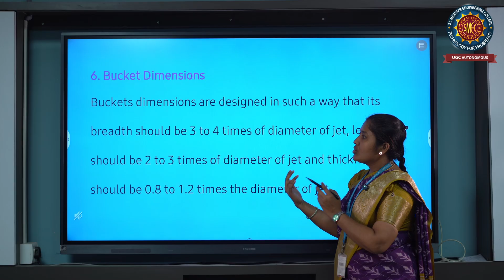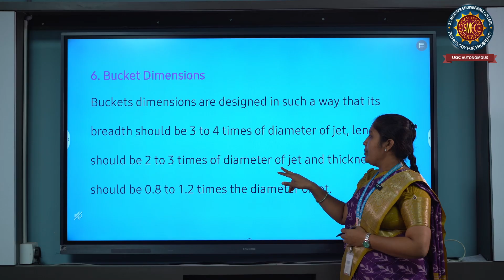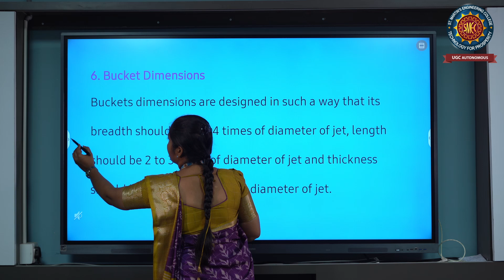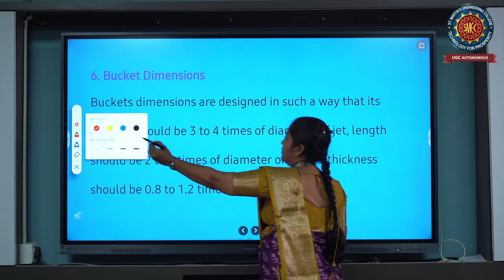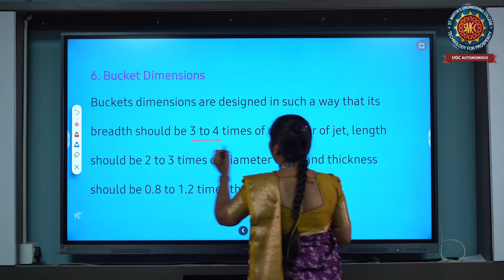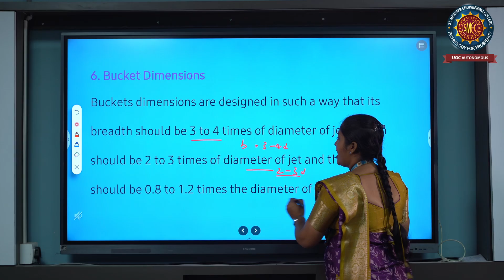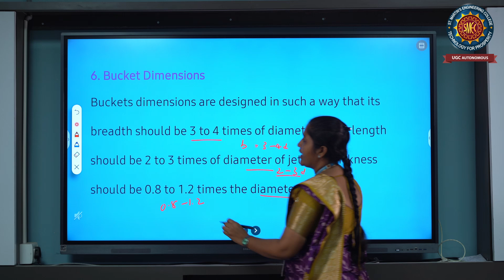And the next is the bucket dimensions. The bucket dimensions completely depend upon the width as well as the breadth. The width should be between 3 to 4 times the jet dia, that is 3 into d, and the length L should be 2 to 3 times the jet dia. So for the breadth, B should be 3 to 4 times d, and the length should be 2 to 3 times d. As well as the jet dia, we can go between 0.8 to 1.2, this is the jet dia.